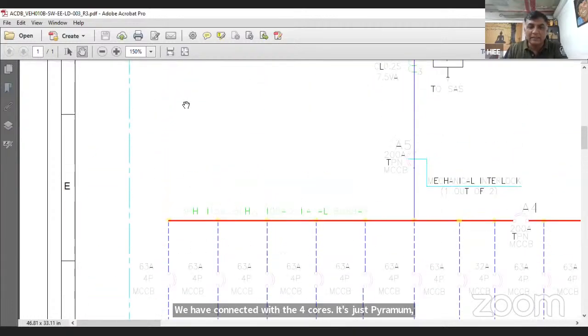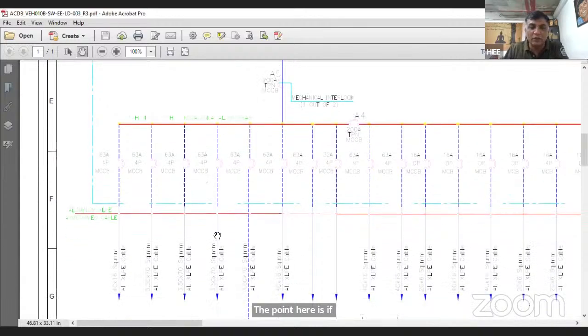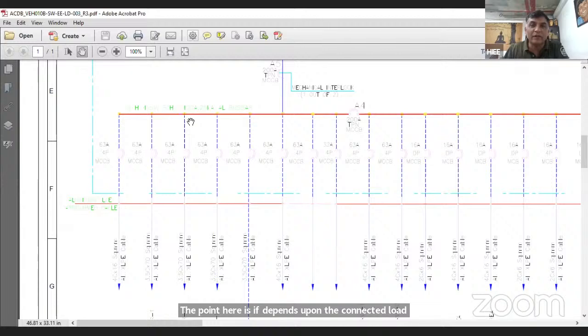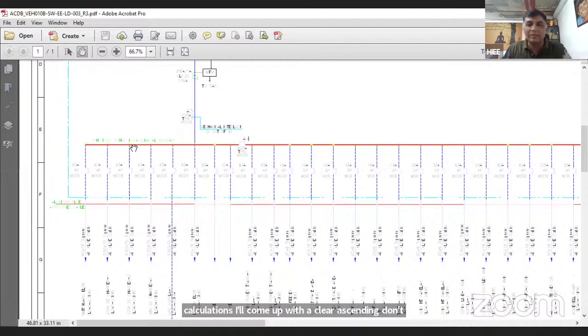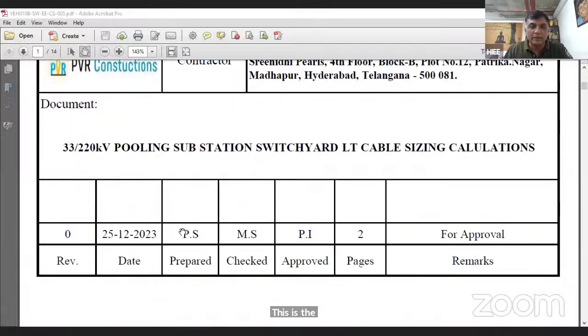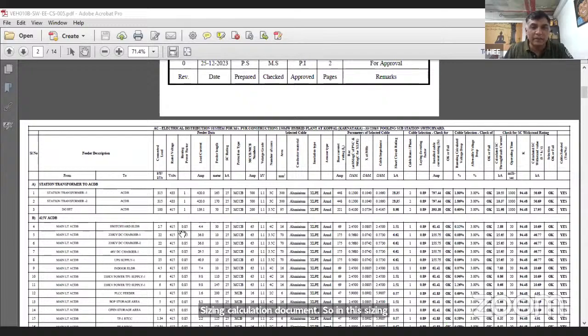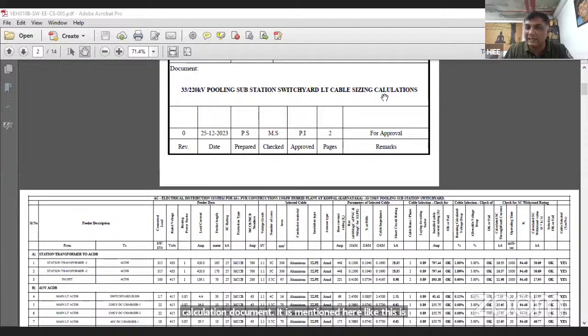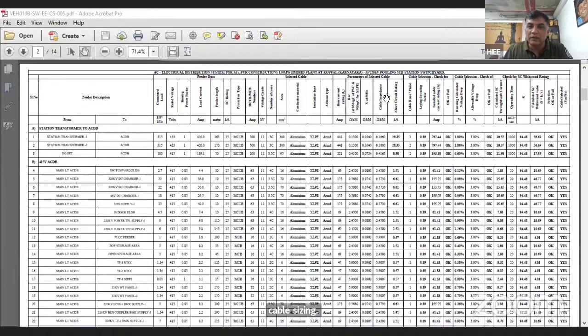So the point here is, it depends upon the connected load, which load you are connecting and what the application of the load is. I know this is not visible clearly, but I'll show you another SLD also. Tomorrow while doing the sizing calculations, I'll come up with a clear SLD. Don't worry guys. I just want to make you understand the importance of cable selection and what sort of cables we are using. This is a single line diagram. And here this is the sizing calculation document. In this document it is mentioned: 33 by 220 kV pooling substation switchyard LT cable sizing calculation. This is how we generally use the documents.